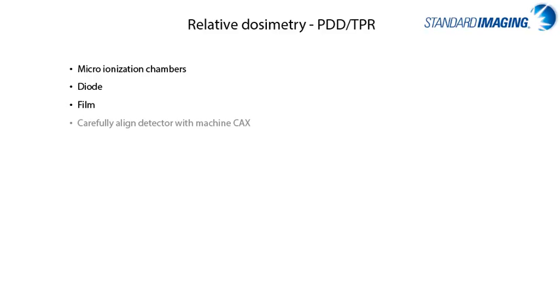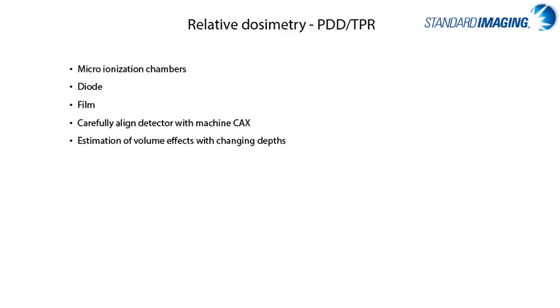Listed here are the most commonly used dosimeters, such as chambers, diodes, film, and all of which must be carefully aligned with the machine's central axis, and changes to volume effects along with perturbation factors should be considered when taking measurements at a variety of depths with a percent-depth-dose-style measurement, or PDD curve.